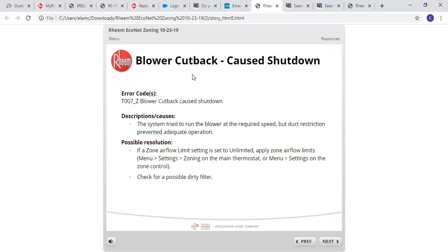This is a big one. Blower cutback caused shutdown. T007Z, blower cutback has caused shutdown. The cause description: the system has tried to run the blower at the required blower speed, but the duct restriction prevented adequate operation. You'll get this same cutback on other communicating systems, the furnaces and the air handlers.